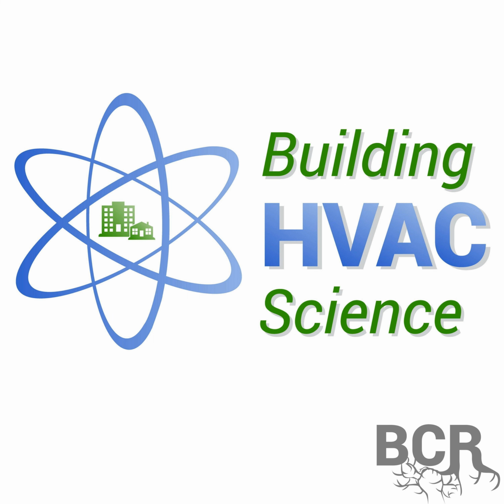Thanks, Bill. You're welcome. I do want to reiterate that the right way to do a balancing is to do a Manual J and to find out what the loads are in each room and how much air is required, and then balance it accordingly. I think the only reason this family was comfortable at all with how poorly balanced the system was is because they had a pretty good shell on the house, 2x6 construction and pretty good air tightness. Had they not had that, I think it would have been unbearable.